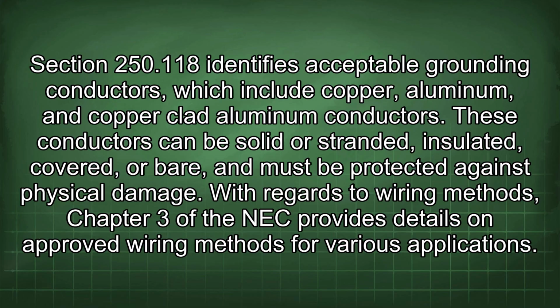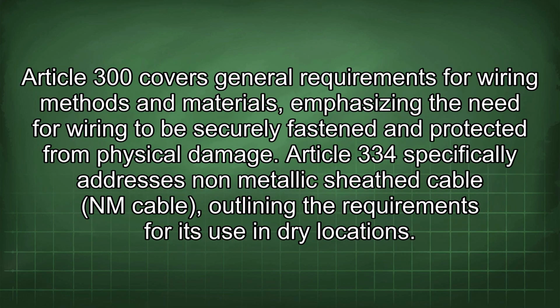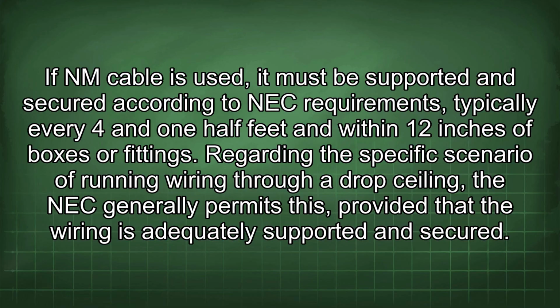With regards to wiring methods, Chapter 3 of the NEC provides details on approved wiring methods for various applications. Article 300 covers general requirements for wiring methods and materials, emphasizing the need for wiring to be securely fastened and protected from physical damage. Article 334 specifically addresses non-metallic sheathed cable and NM cable, outlining the requirements for its use in dry locations. If an NM cable is used, it must be supported and secured according to NEC requirements, typically every 4½ feet and within 12 inches of boxes or fittings.